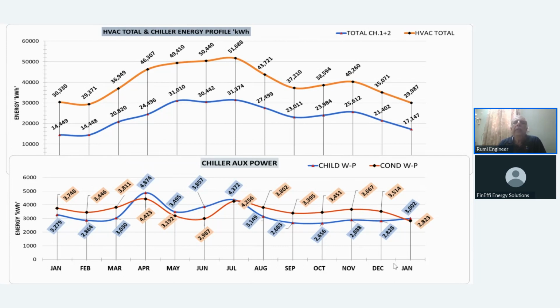But chiller loading, unloading, and operational efficiency also depend on your condenser water pump, cooling tower, and chill water pump, because nowadays everything is installed with VFD. Again, everybody thinks that putting up a VFD is a panacea, like taking a pill for all illness.